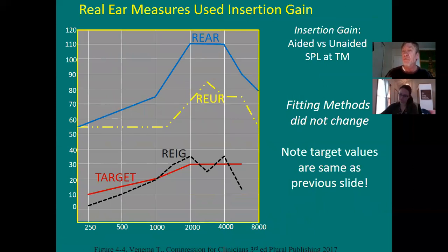Step number 2. Here you're looking at insertion gain. What they did here was measure the guy's unaided open ear canal resonance, the resonance of the outer ear. They put a tube in the guy's ear canal, and you snake that tube all the way up to his eardrum. Don't touch the drum, he'll feel it. You have the open unaided ear, and the guy is sitting 18 inches away from the screen monitor of a computer. What comes out of the speakers is a sweep tone.